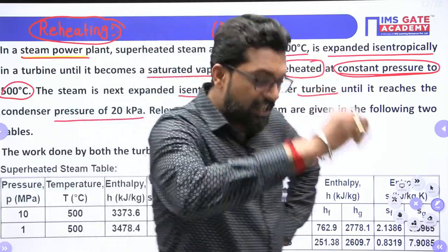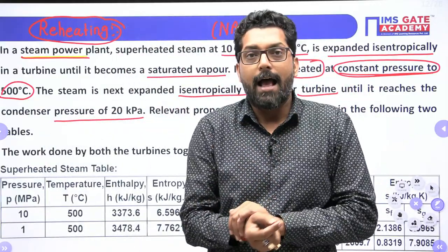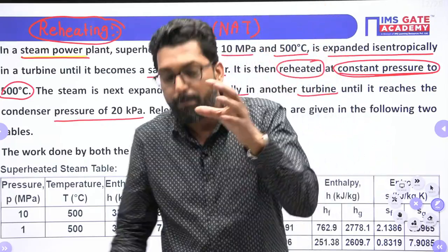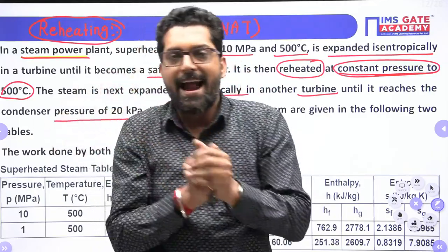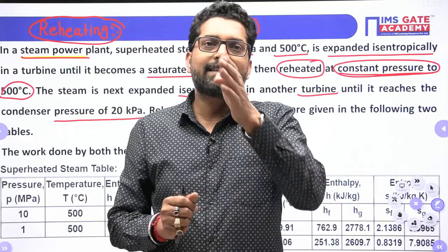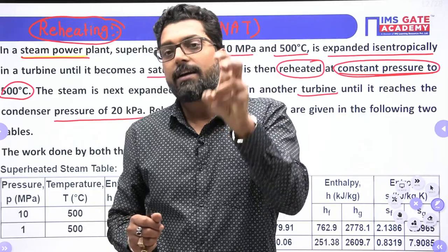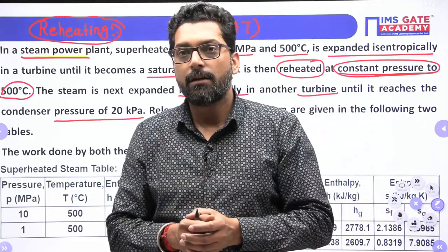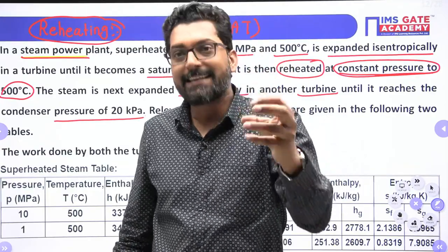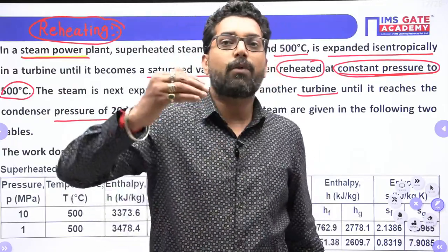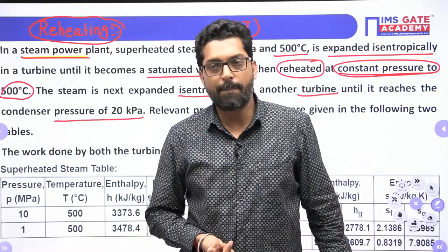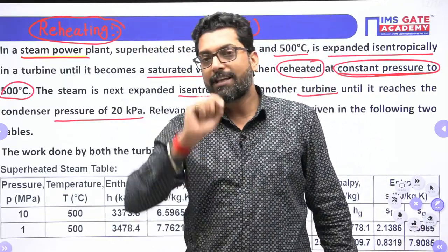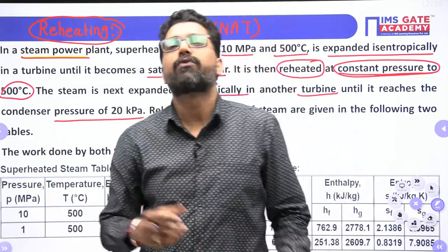When the steam comes out from the boiler and enters the turbine, the steam is a combination of water particles and water vapor. If the quality is poor, there is a high content of water particles in that mixture. If the flow velocity is very high, the vapor particle is lighter than the water particle, so the inertia of the water particle is more. At the same velocity, the water particles strike the turbine blade with more energy. So there may be pitting or distortion in the turbine, or failure of the turbine blade.